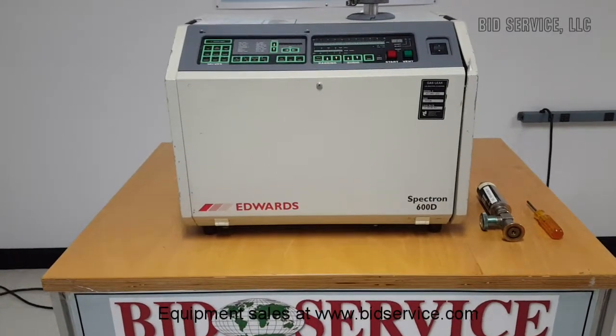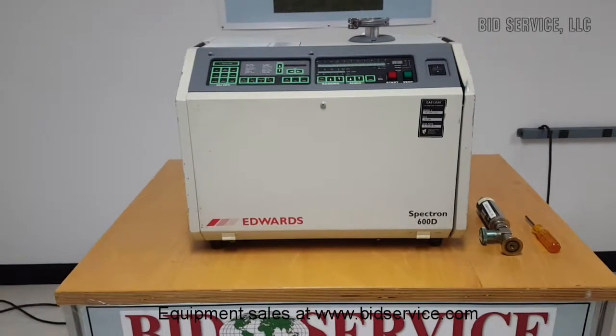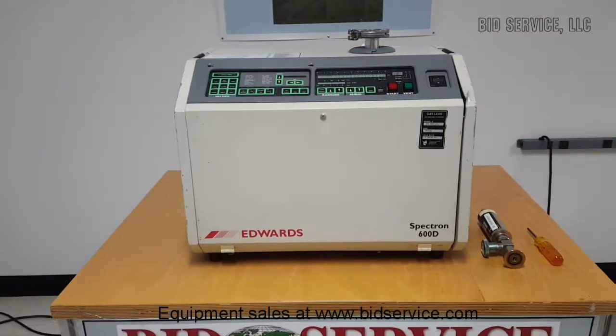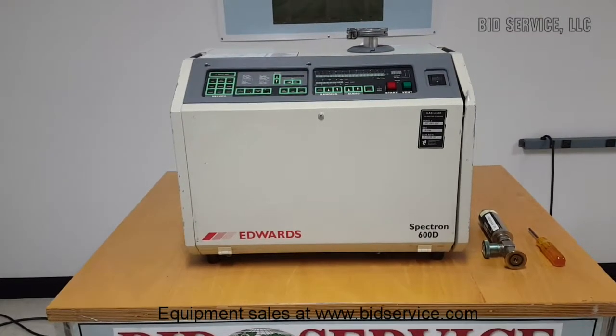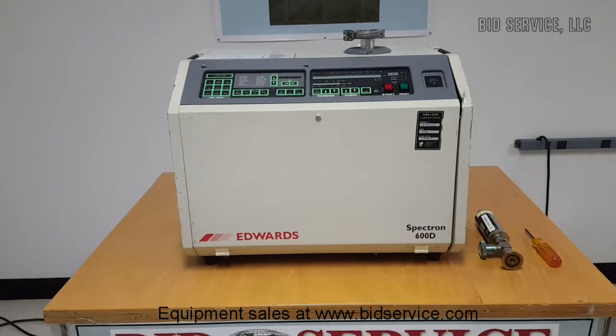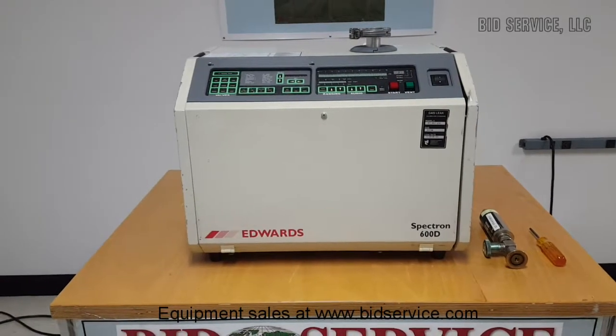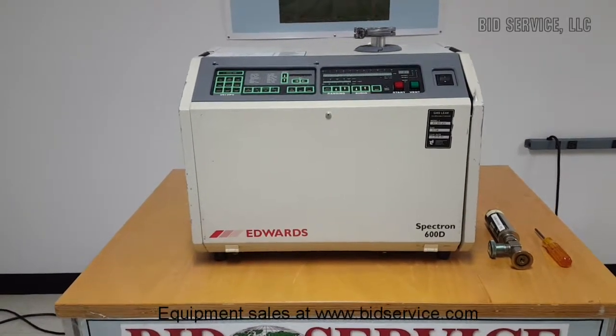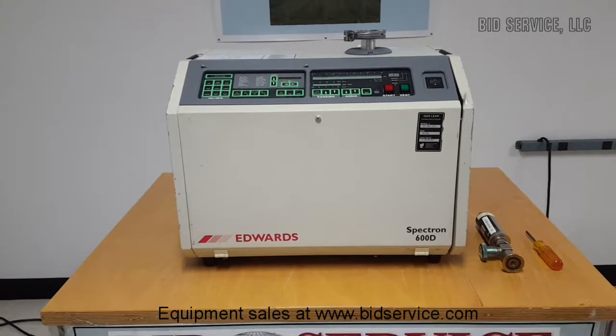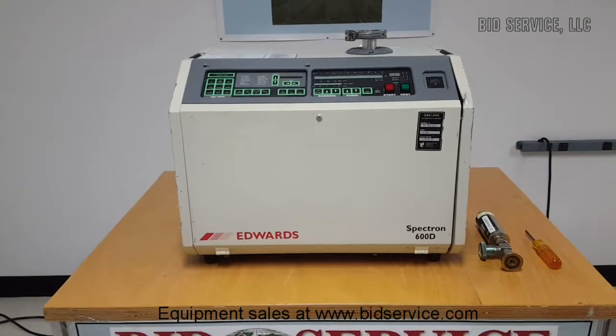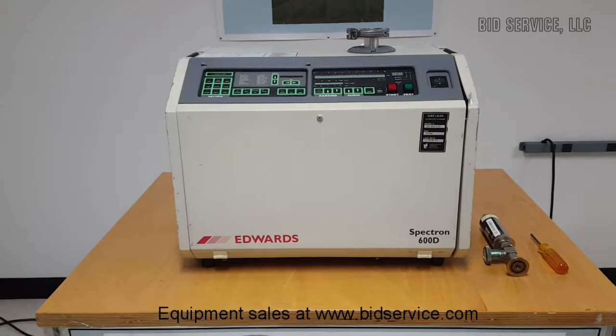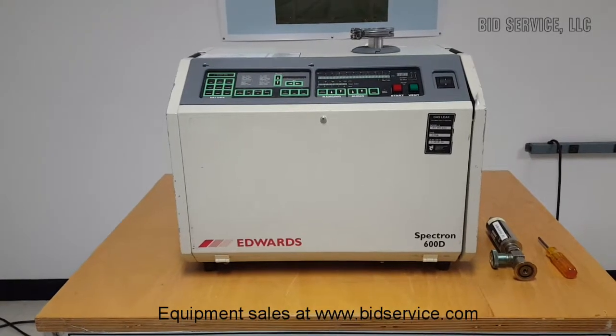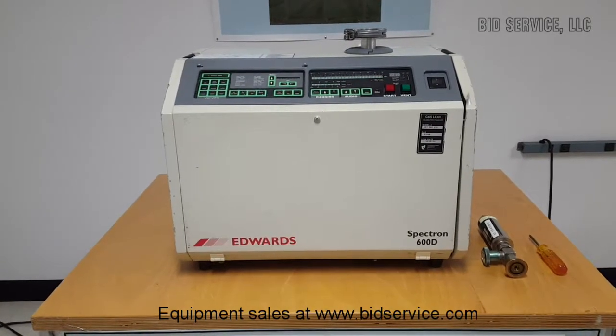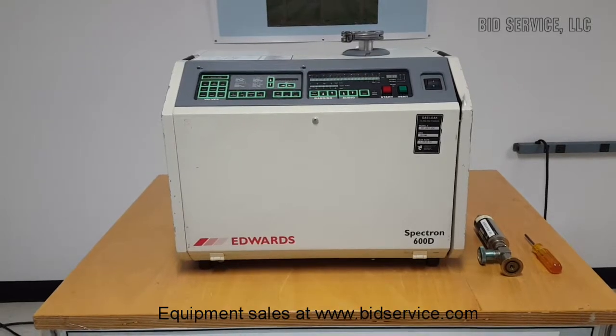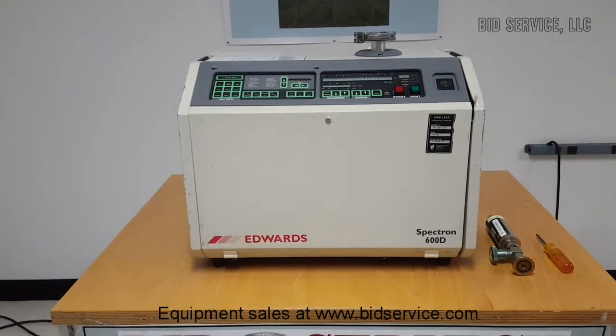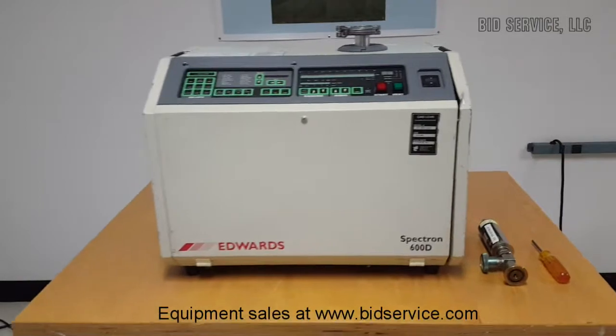It has a leak range of between 10 to the minus 4 millibar liter per second to 6 times 10 to the minus 11th millibar liter per second, and has both direct and reverse flow in a single unit. It is powered by 115 volts, 60 hertz, 10 amps. Let's take a look at some of the features. First, let's take a look at the rear connections.